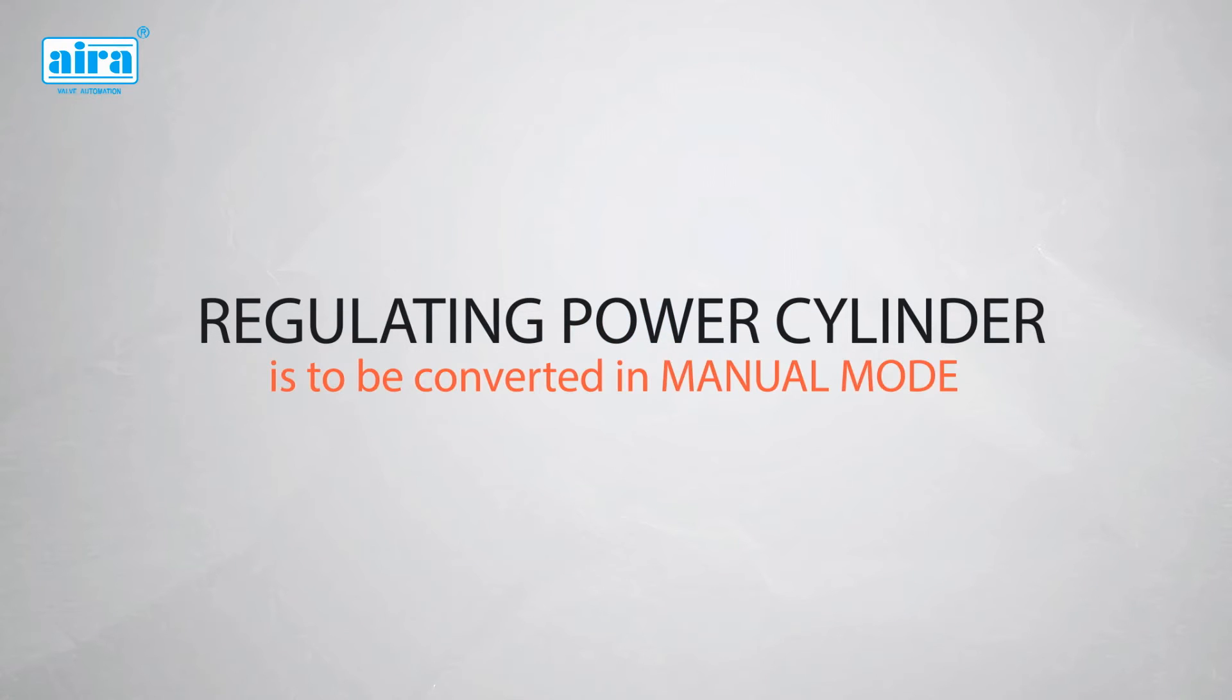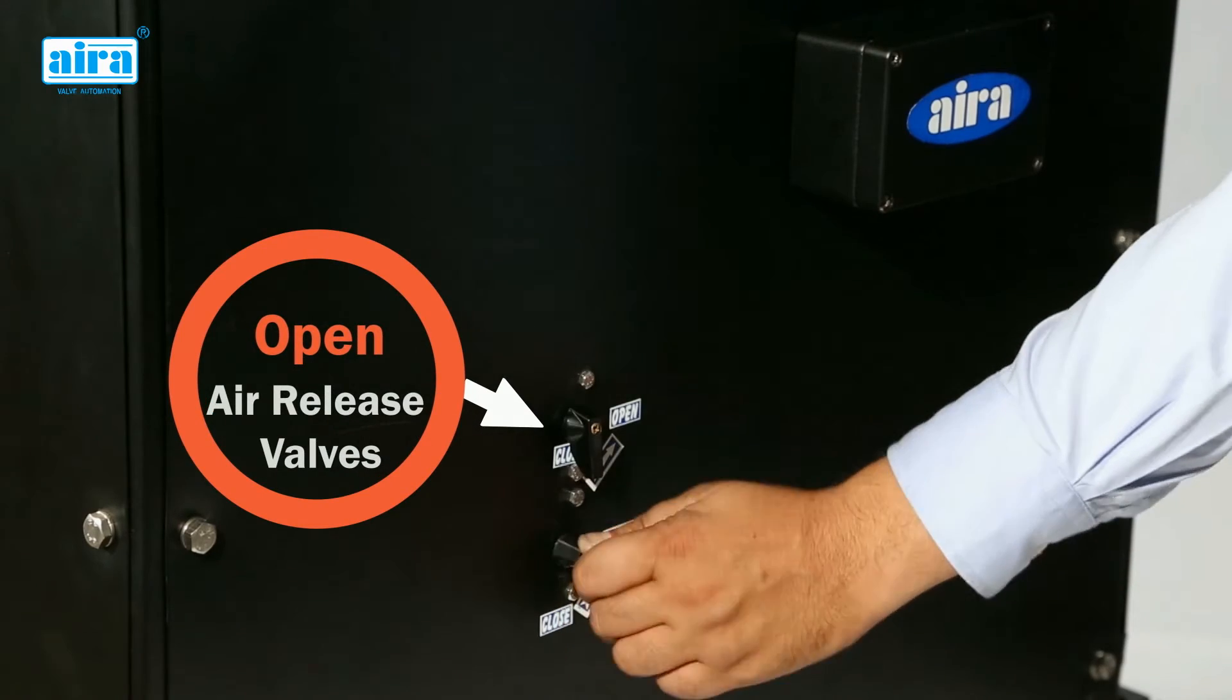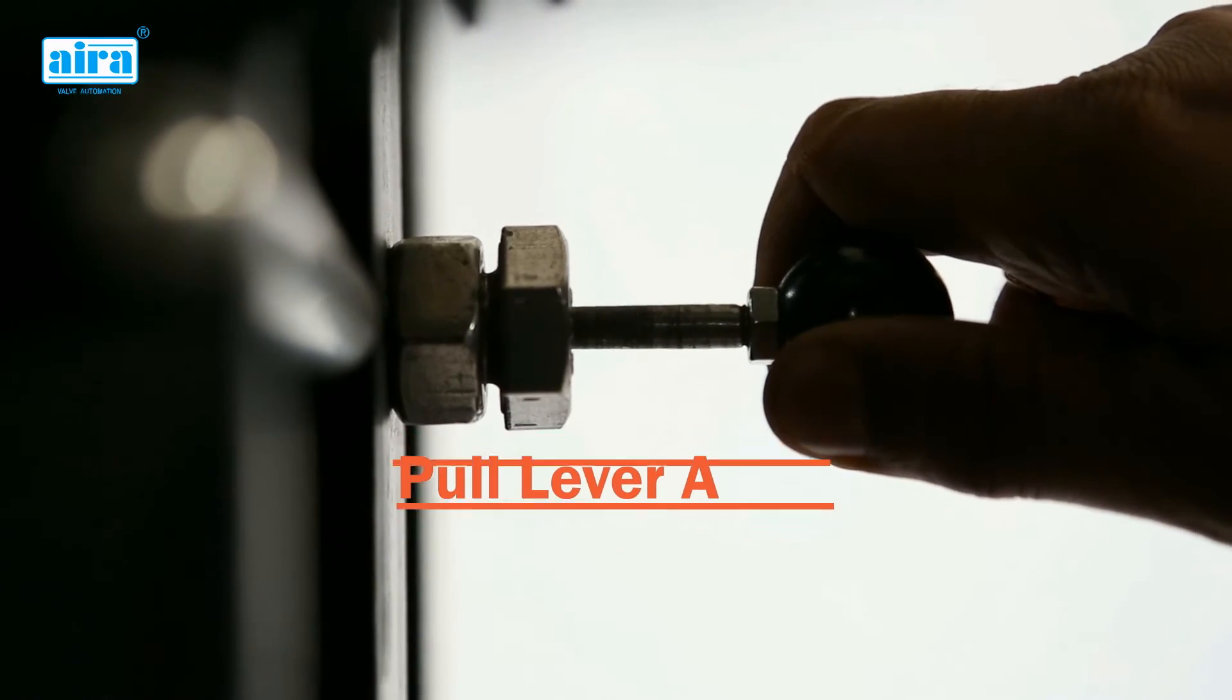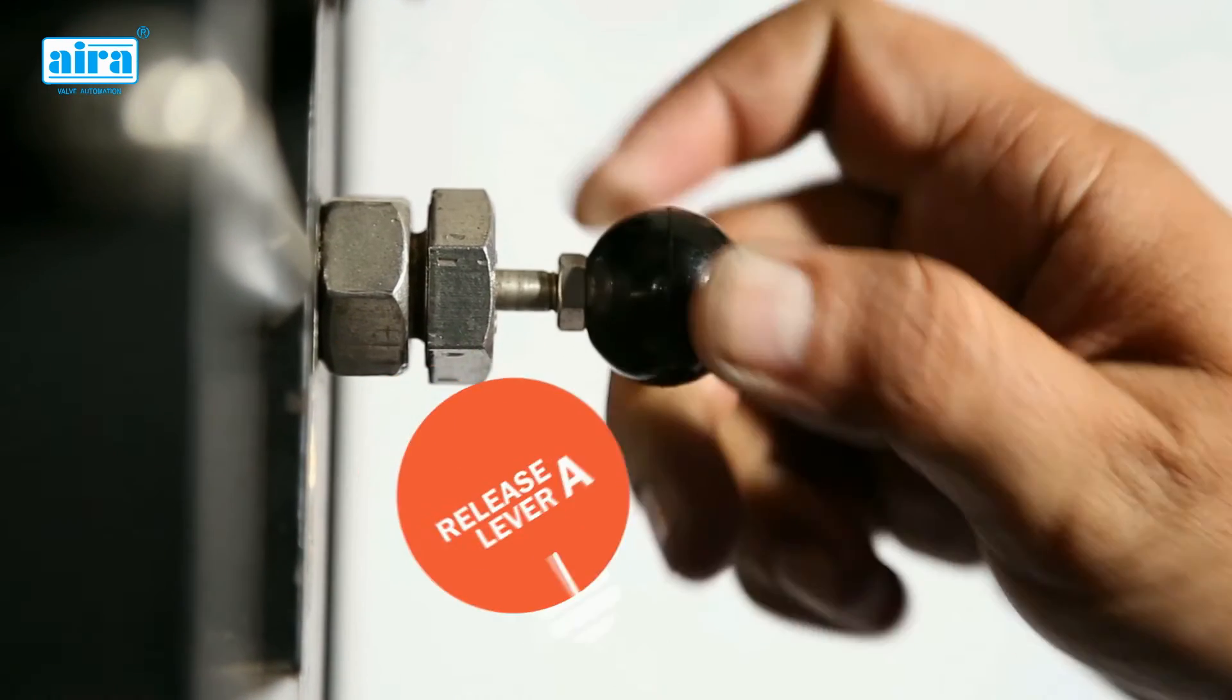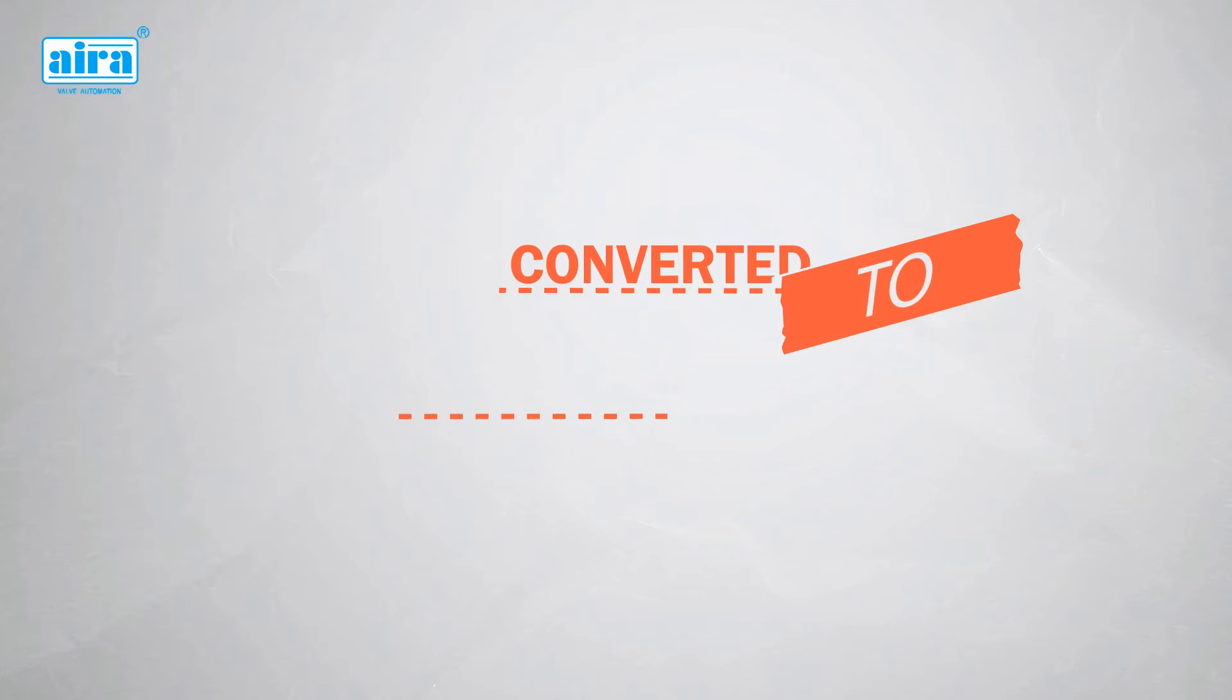If the RPC is to be converted to manual mode and then again to auto mode, both the air release valves need to be opened first. Then pull lever A and engage the clutch by pulling lever B with hand wheel and then release lever A. This is how it can be converted into manual mode and can be operated by lever B manually.